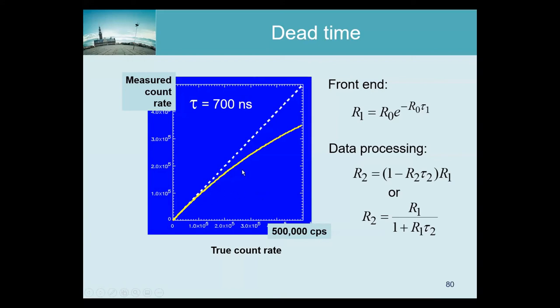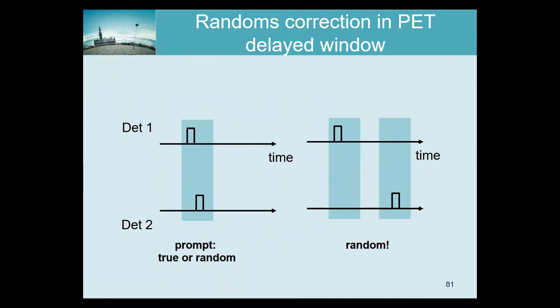This can happen clinically, for example during a dynamic scan with a bolus injection, where all the activity arrives almost simultaneously in the heart. If you are imaging the heart you then see a huge dose and even a good system may saturate at that time. In principle it is corrected, but the correction breaks down at very high count rates. Current systems are pretty fast, so it should normally not be a problem.